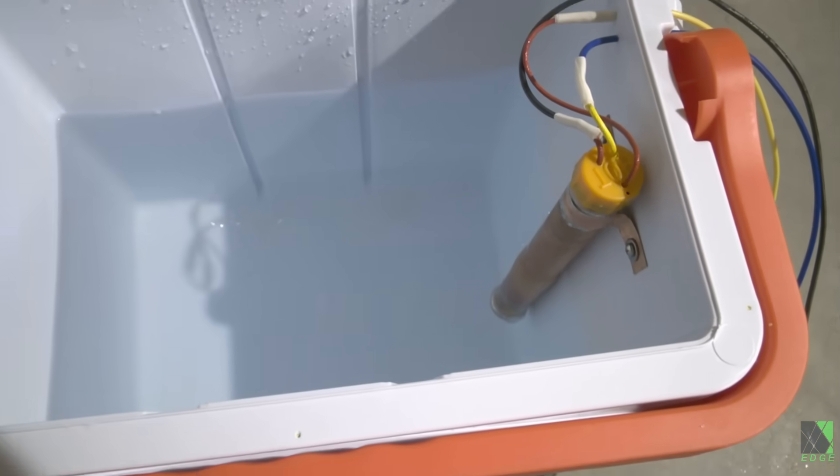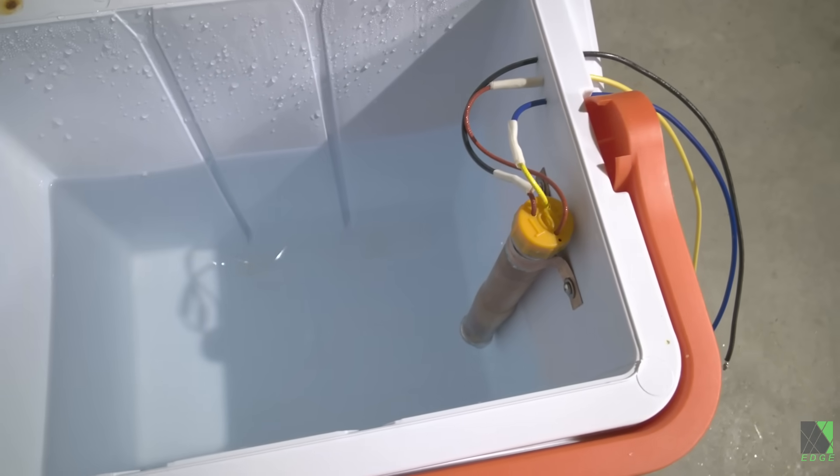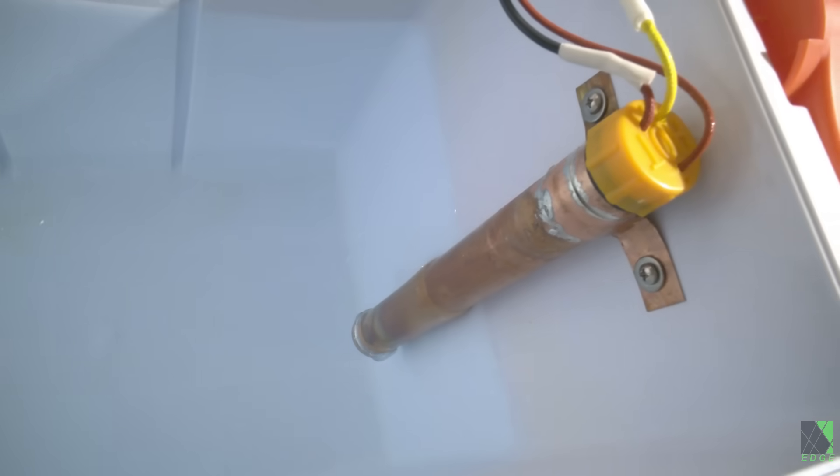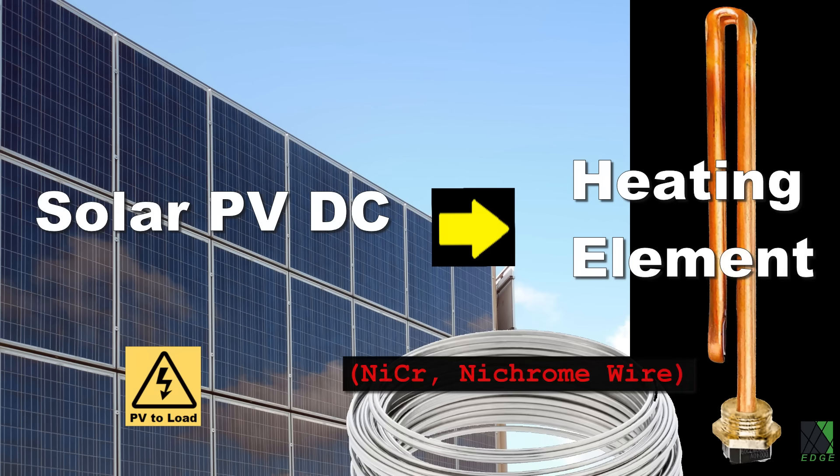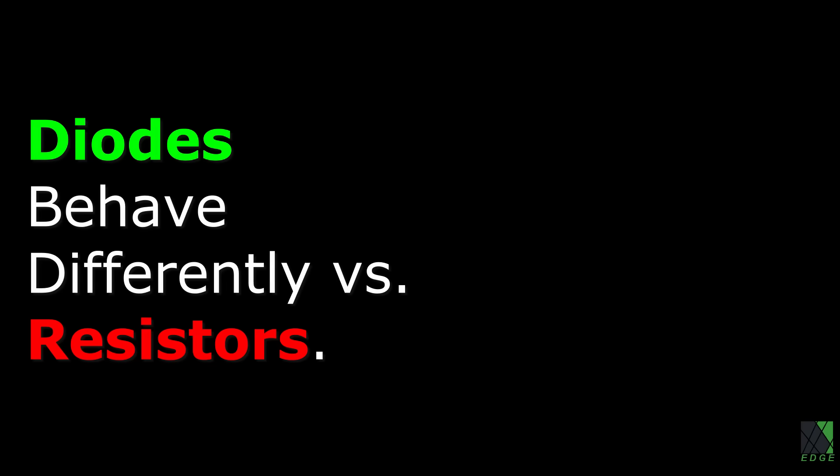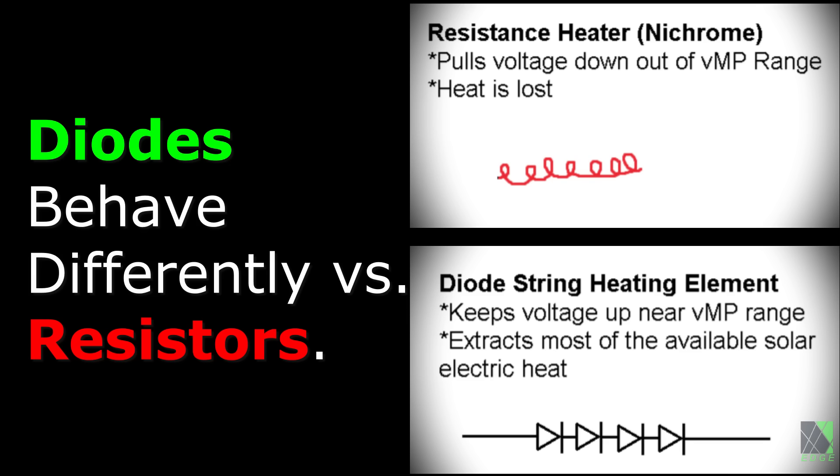What we're looking at here is the second version of a prototype solar electric immersion hot water heating element. It uses semiconductor technology—in other words, it's a diode chain. A traditional nichrome or Kanthal A1 resistance heating element can be directly attached to a solar panel to make heat, for example in a residential hot water heater. A diode chain heating element is not based on resistance and does not behave like a resistance heating element.